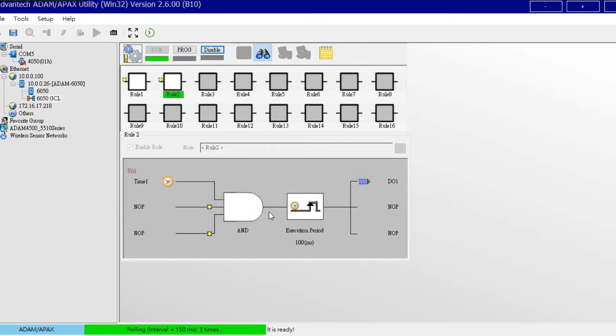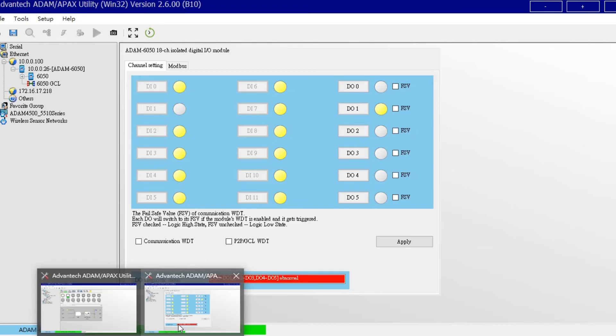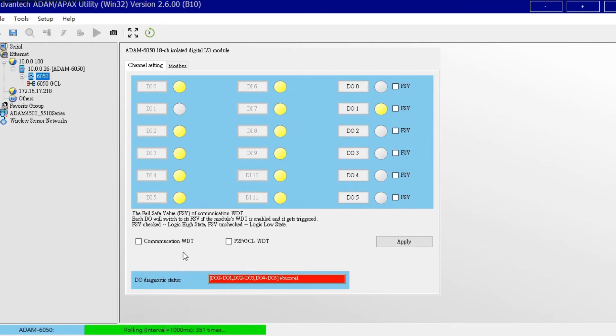When we short DI channel 1 by dry contact, DI channel 1 will get logic low, and we can see timer 1 counting in Rule 2. It will trigger DO1 after 3 seconds. The yellow dot indicates which execution stage GCL is currently reaching. We can open a second utility window to check the result of GCL. This is the first example — a simple test to learn the GCL function.